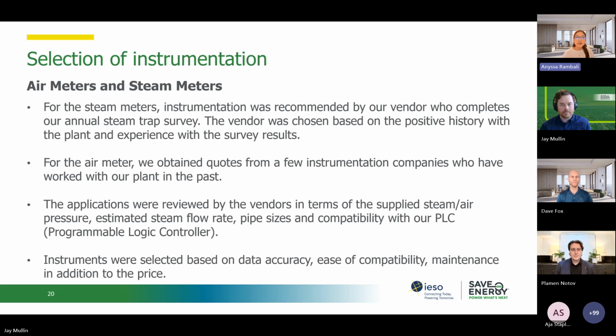Our air meters were chosen based on a few instrumentation companies we worked with in the past who had recommendations. Applications were reviewed by these vendors with us in terms of steam, air pressure, estimated flow rate, pipe sizes - whatever we knew at the time from our systems - and compatibility with our PLC, our programmable logic controller. The instruments are selected based on data accuracy, ease of compatibility, maintenance, and cost.